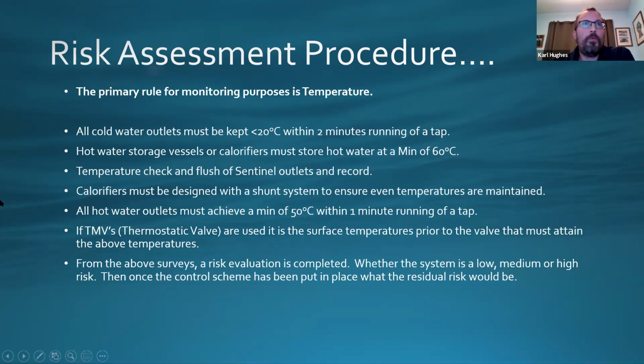So what we've got here is the primary rule for Legionella control is the temperature. So what you're after on this side of things here is, as we mentioned before, to make sure you get the cold water to the outlet. So the tap that you turn on has got to be below 20 degrees within 2 minutes. This doesn't mean that you have to keep running it for 2 minutes and then logging it. It needs to be brought down within there. And if it starts plateauing out, then obviously that's the temperature you take for the cold water side of things.